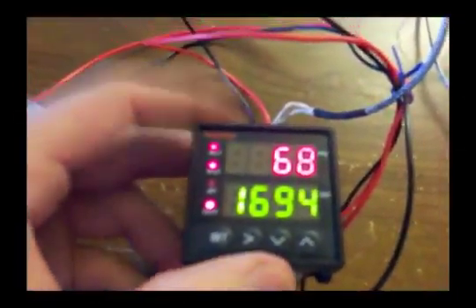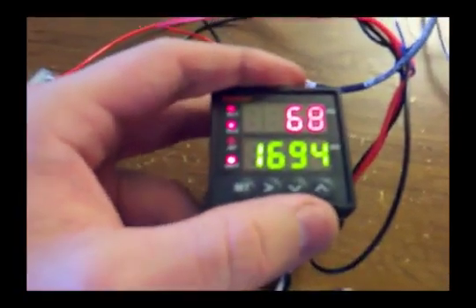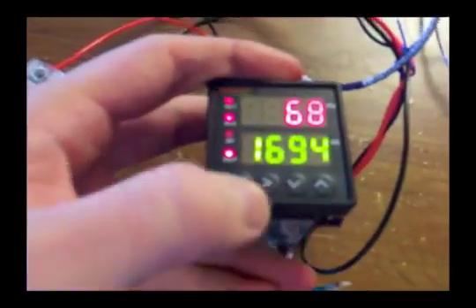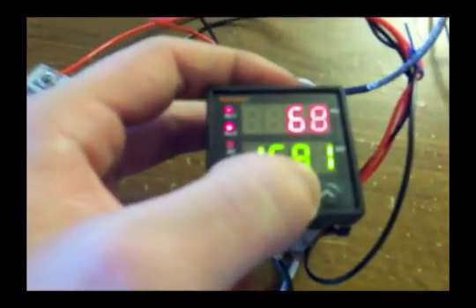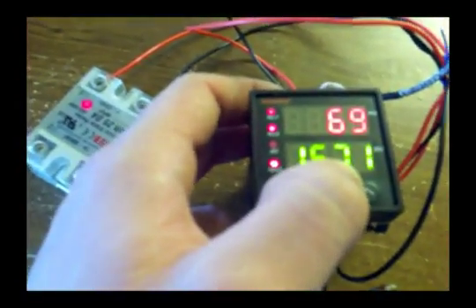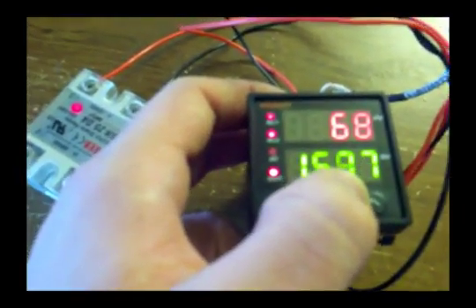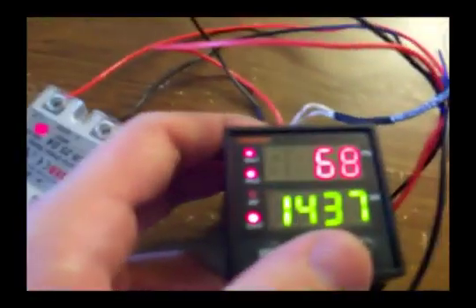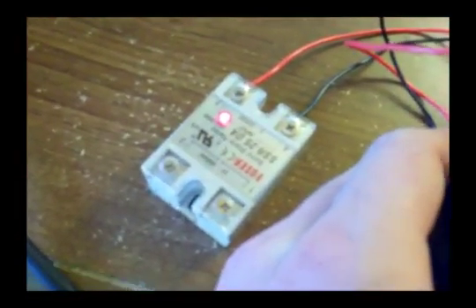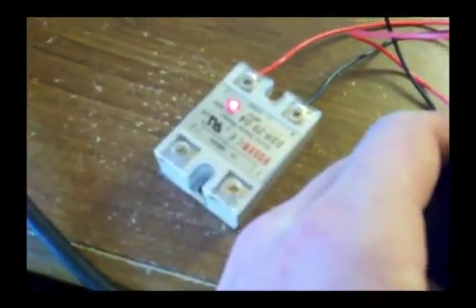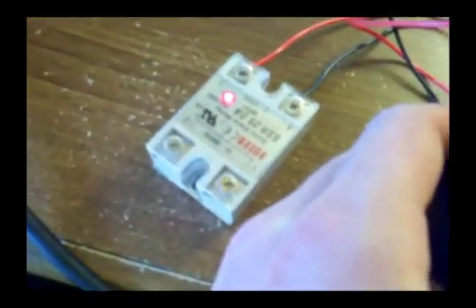So what you see here, the sixty-eight is the process value. That's the actual temperature it's measuring from my room, and the bottom value is the set value. I can tell it to go to whatever I want it to go to. But since it's not connected to my heating element right now, it's not going to matter. It doesn't matter where I put this value at right now. But what does matter is, if this set value is higher than my measured value, that little light should be on because it should be telling my solid-state relay to allow power from my power source to the heating element.